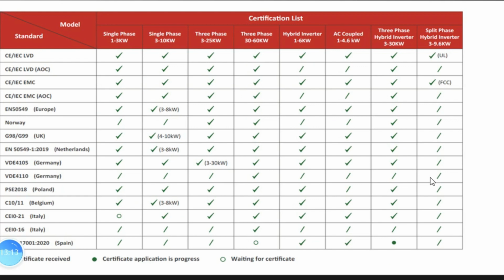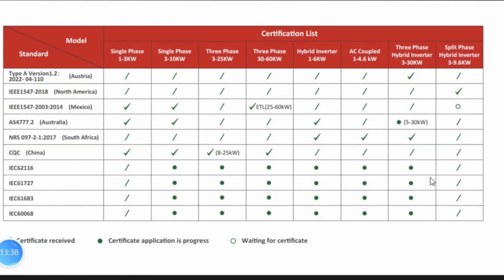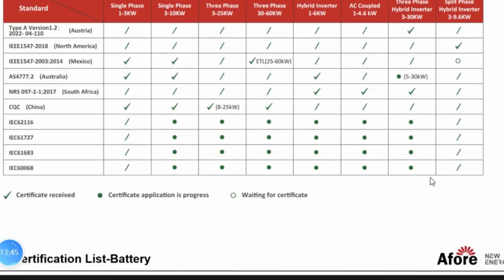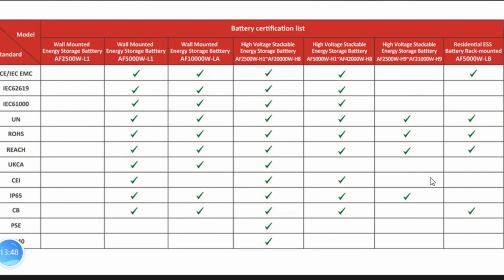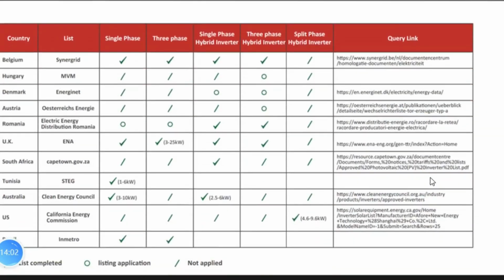For the inverter certifications, regarding the safety standard, grid connection standard, and EMC standard, for many different countries: for most European countries, EN 50549, for Norway, UK, Netherlands, Germany, Poland, Belgium, Italy, and Spain. Also Mexico, North America, Australia, South Africa, etc., and IEC standards. This is the certificate list for batteries. Batteries need far fewer than inverters, mainly the CE, IEC safety standard, UN, UKCA, etc.